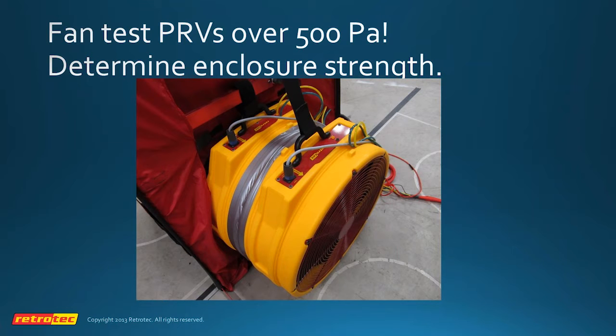This is a fan system that we evolved, which is actually two of our door fans in series running in opposite directions, but blowing air in the same direction, and it's called the contra mode. This is the first one that we created. You can actually bring the room up to as much as 500 pascals to prove to somebody that the room will actually hold 500 pascals. In some cases, they want to be conservative. They want to put a 100 pascal limit on it or whatever. In one case, when they did that, I took it up to 500 pascals. They said, well, it's holding 500 pascals now, so therefore it should be fine.